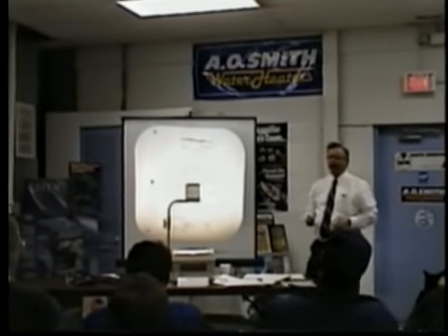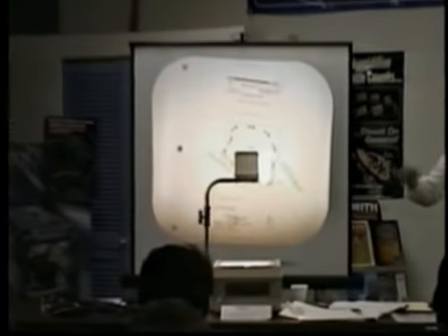And you have to know that, because when you hook up instruments, you have to put the negative hose in the return. Because if I do the same thing in a supply, drill a hole and put the tissue paper over it, would it get blown away or sucked in? Blown away. We call that positive pressure. The basics: returns are negative, supplies are positive. Okay?